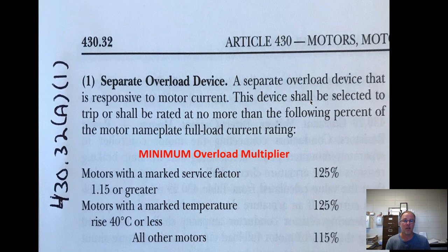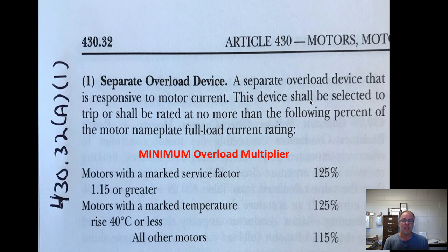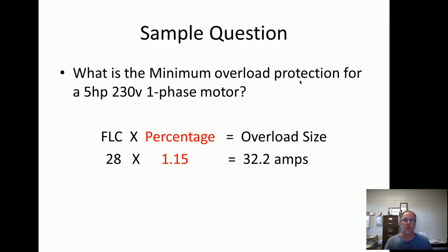So basically, this step: take your full load current and you've got three multipliers — 125%, 125%, or 115%. That's for minimum. If the question asks for overload protection without specifying, you use minimum. If it says minimum, you use minimum.